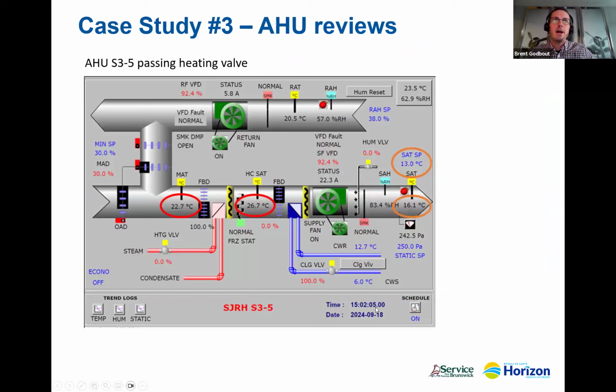This is passing heating valves that we found. Operators will do their own checks, daily checks of their HVAC unit. I also do them as well because they can get busy. Competing priorities can make it difficult to always get to these things. And a passing heating valve is something that sometimes folks will be like, it's just a passing heating valve, no big deal. But as you're going to see in this case, it can be compounding effects, and it can be more than it appears.